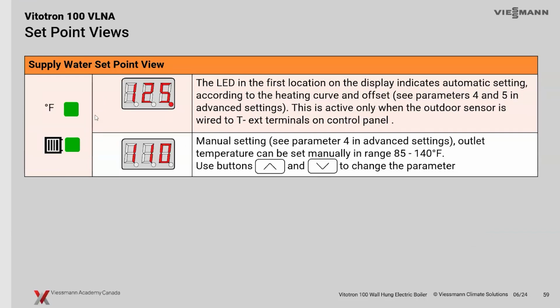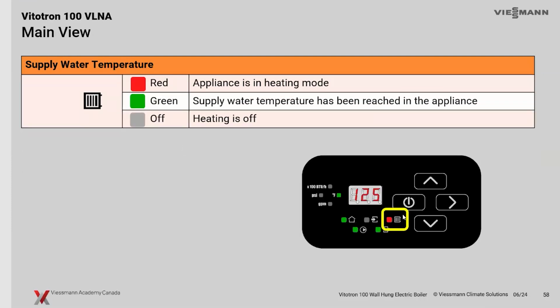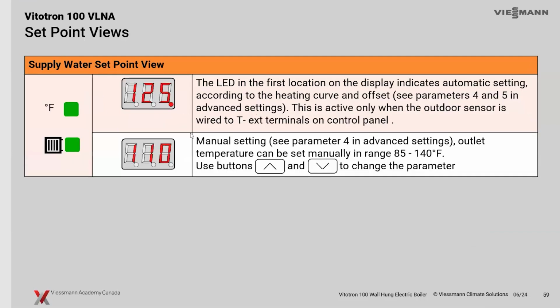If we want to make an adjustment to it, all we have to do is go to that particular area of the unit. So hit this little button, hit your little arrow key until you're highlighting the little radiator here. And I can use the plus or up and down buttons here, and I can change that if I'm going to fix set points. So if I'm at 110 and I want to change it to 120, I just have to use the right arrow key until I'm highlighting this little symbol. And once I see the temperature here in Fahrenheit, I can increase or decrease it. Then once I move on from there, it's just going to accept that new temperature. So very simple to make your adjustments on the fly.